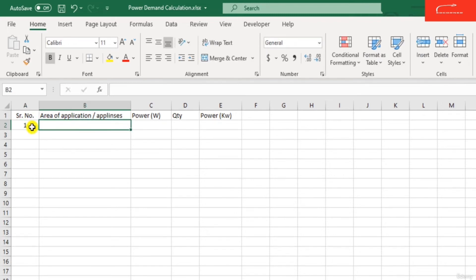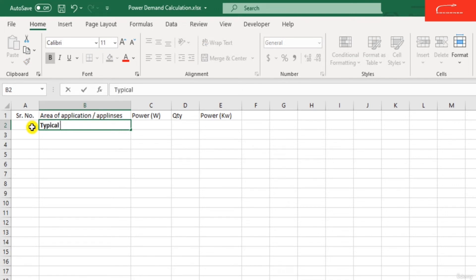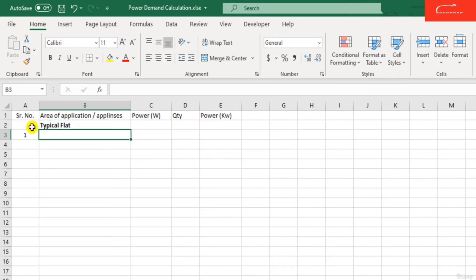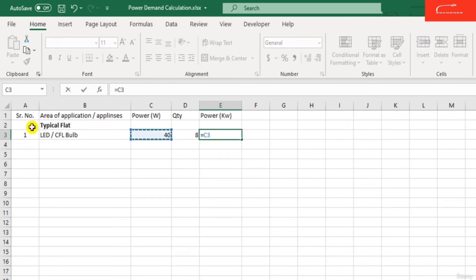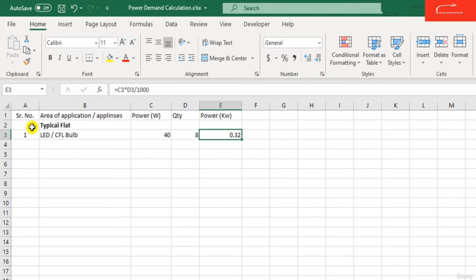For serial number 1, we calculate the power required for a typical flat in the building. Suppose there is one building with multiple typical flats. We need to calculate each flat's power demand. Appliance number 1 is the LED or CFL bulb — the actual power required is 40 watts. Suppose in one typical flat there are 8 CFL bulbs. The total power is watts multiplied by quantity divided by 1000, giving 0.32 kilowatts.